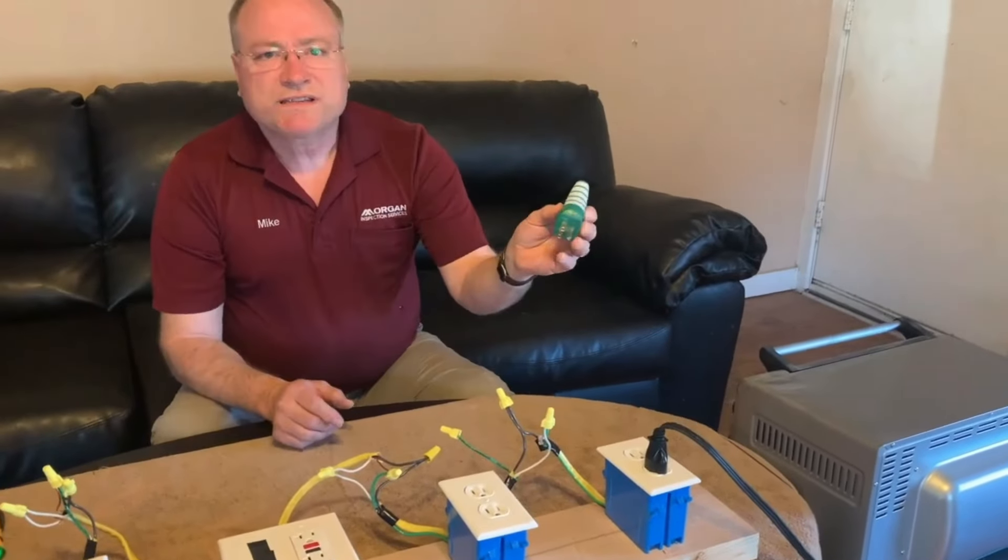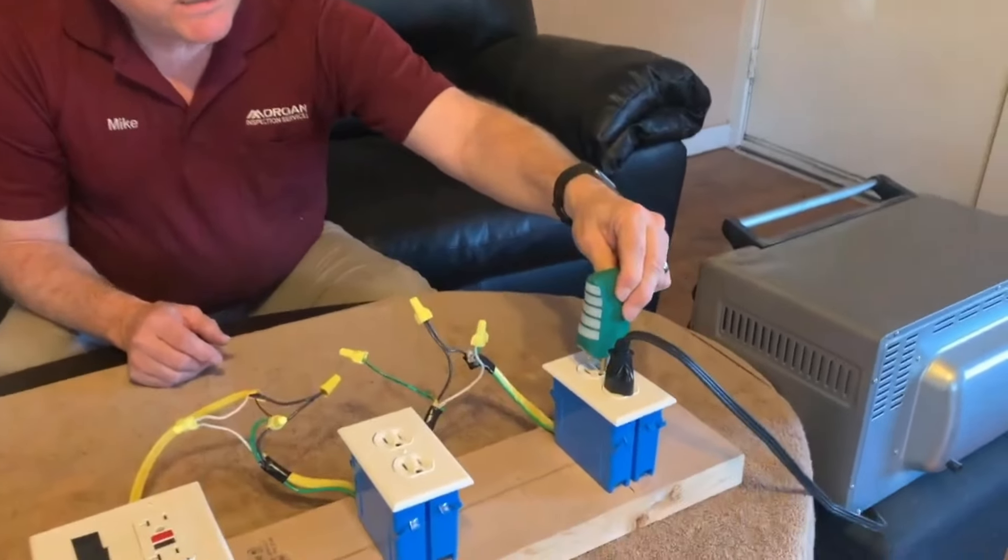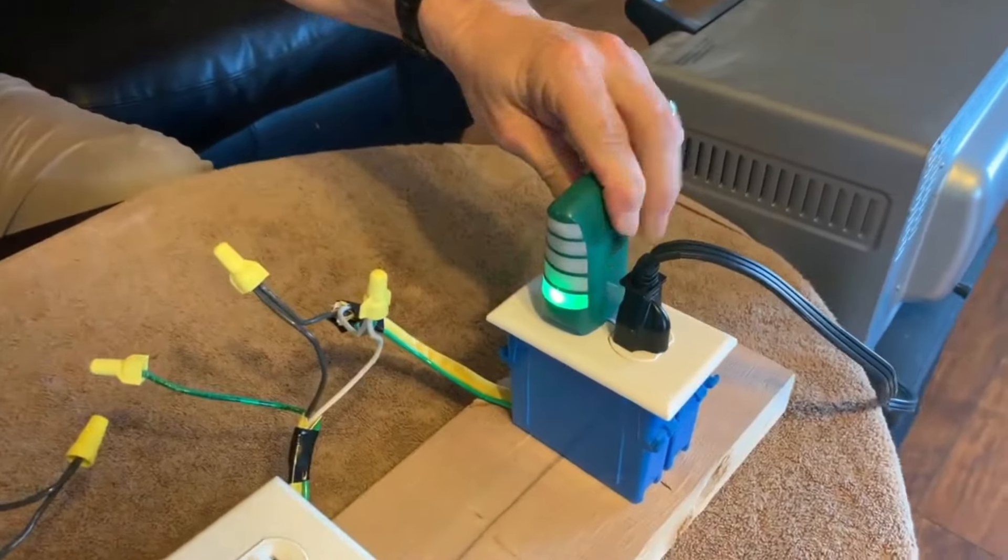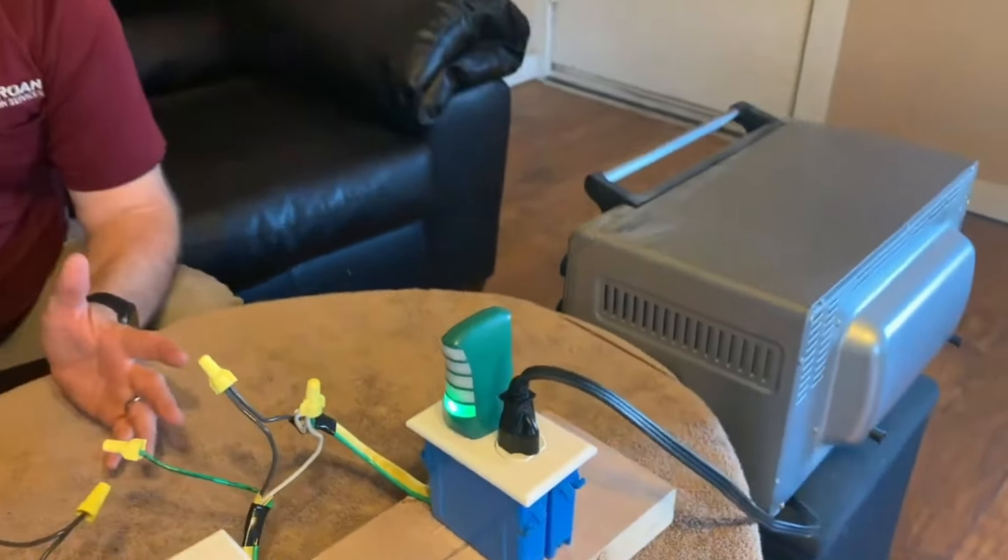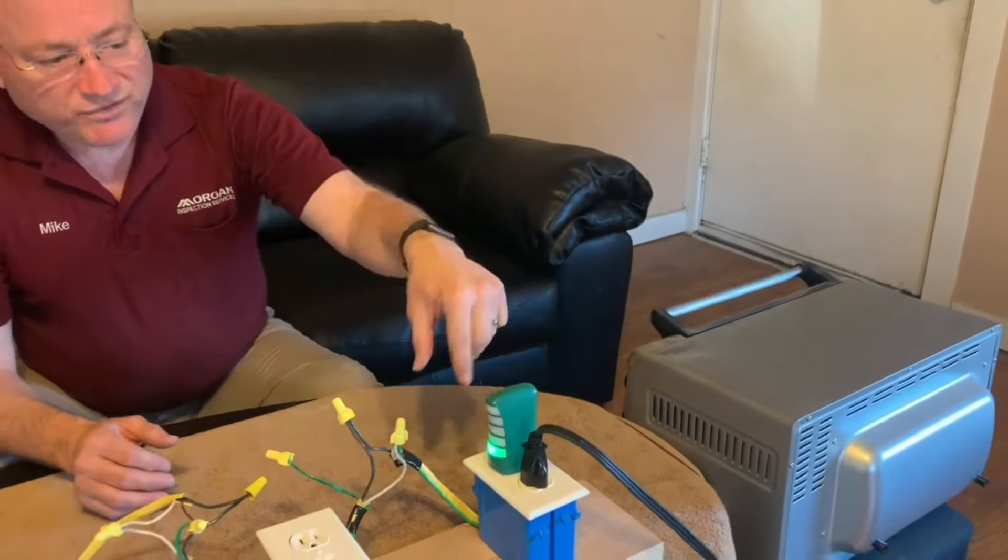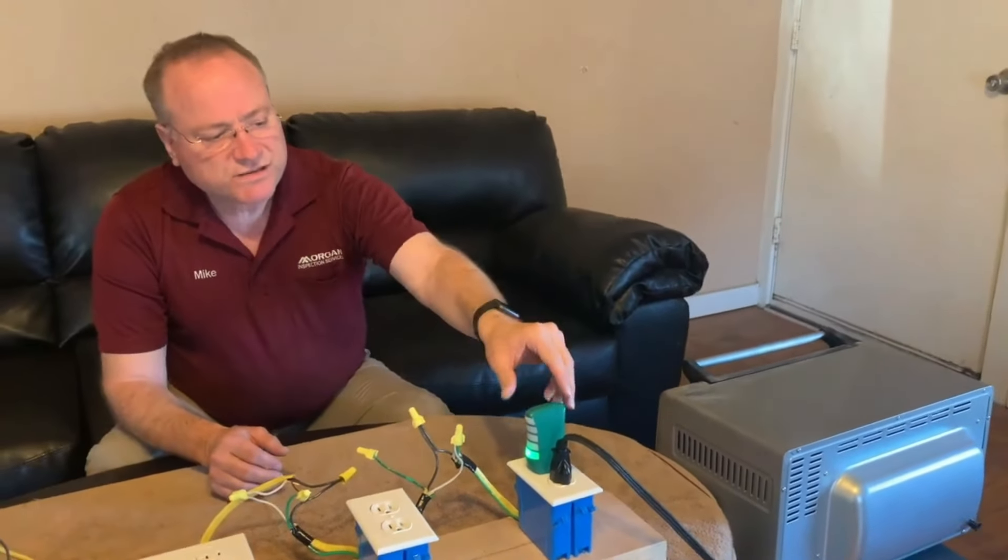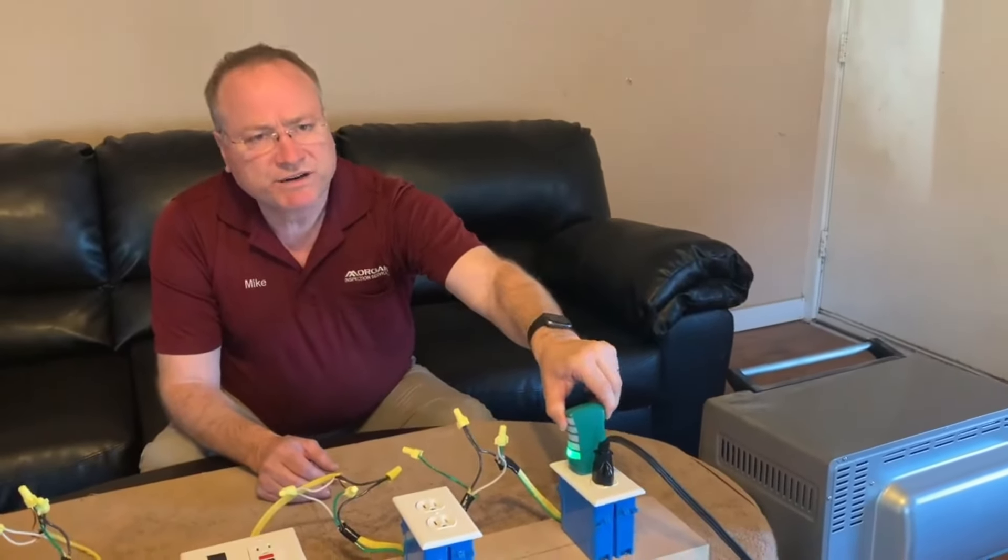If I use one of these standard three light testers to test this electrical outlet, the green light shows that that outlet is properly wired. However, we know it's not. That's one of the flaws with these three light testers is they can't pick up every situation.